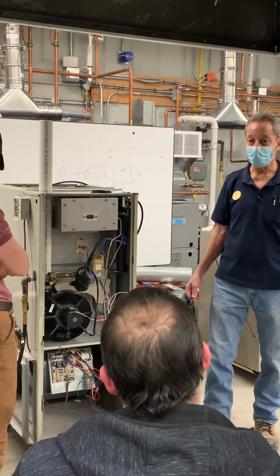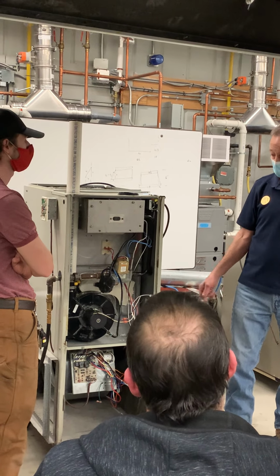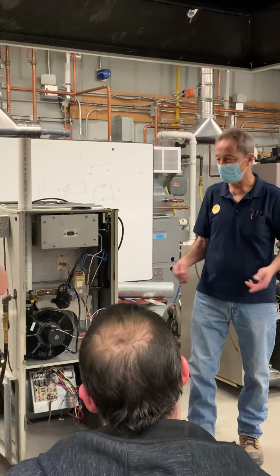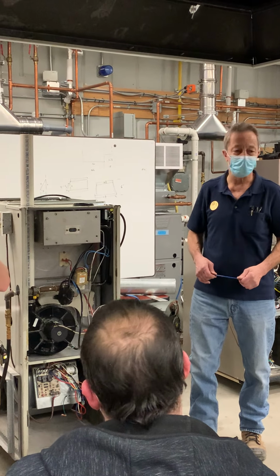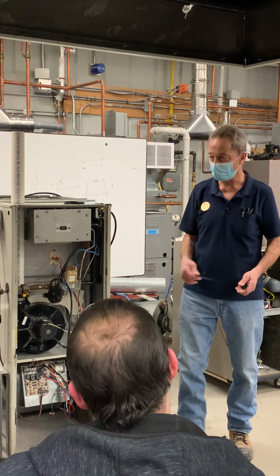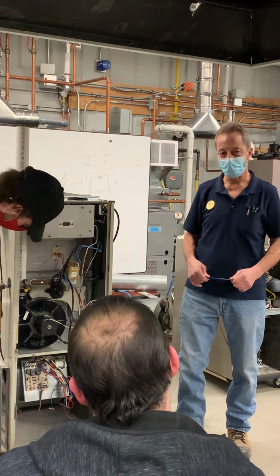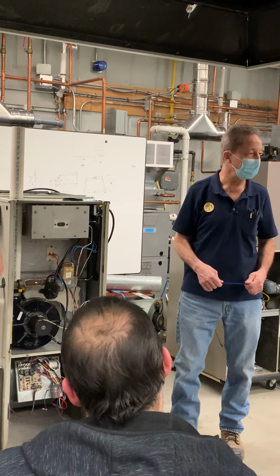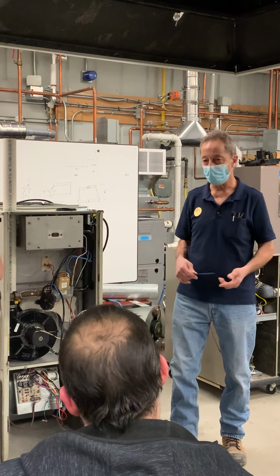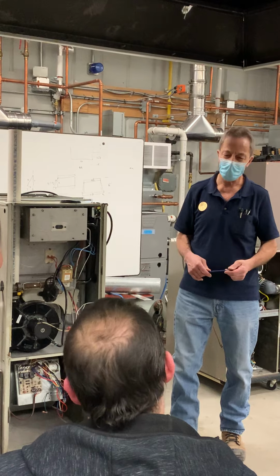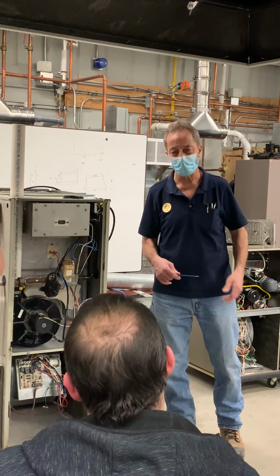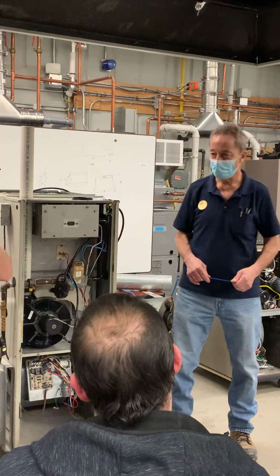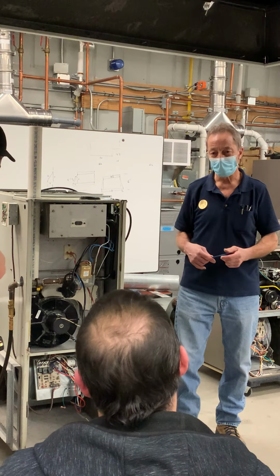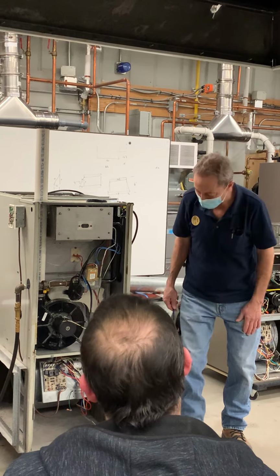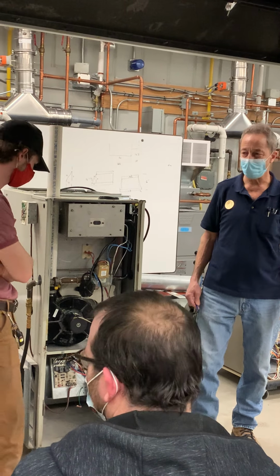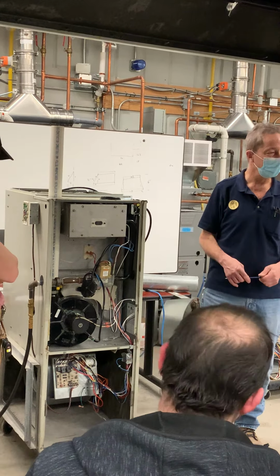But you're gonna feel like an idiot if you change the motor. You tell the customer, oh, I changed the motor because I thought it was the motor, but it didn't fix the problem. I'm gonna try and change something else. Then you change the circuit board. I'm gonna try something else. Then you change the gas valve. So now you're up to about $1,000 in parts. The customer's saying, is it working yet? No, not yet. I'll get there soon. There's only about 10 more parts I gotta check. Okay? But if you know how to... This happens to be the wire, right? Yeah, and then you figure out, oh darn, the wire's not on. Somebody must have taken the wire off or they didn't put it on properly.